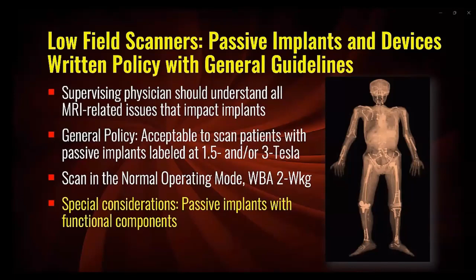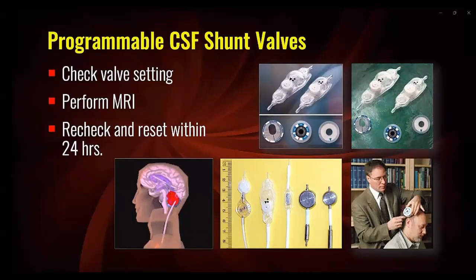To ensure patient safety from an RF field consideration, a margin of safety may be provided to the patient by operating the MR scanner in the normal operating mode, which defaults the whole body average specific absorption rate to a value of 2 watts per kilogram. Special consideration should be given to certain passive implants that have functional components, such as programmable cerebral spinal fluid shunt valves, magnetically activated orthopedic implants, or other similar devices. For a programmable CSF shunt valve, you should follow the labeling conditions that indicate that a suitable healthcare professional should check the pressure setting of the valve before the MRI exam and then recheck and reset the CSF shunt valve as needed after the MRI procedure.